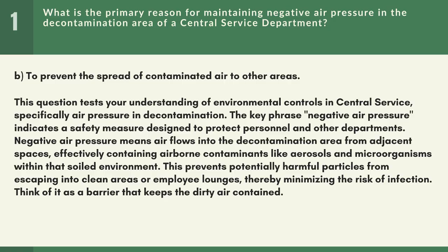Negative air pressure means air flows into the decontamination area from adjacent spaces, effectively containing airborne contaminants like aerosols and microorganisms within that soiled environment. This prevents potentially harmful particles from escaping into clean areas or employee lounges, thereby minimizing the risk of infection. Think of it as a barrier that keeps the dirty air contained.